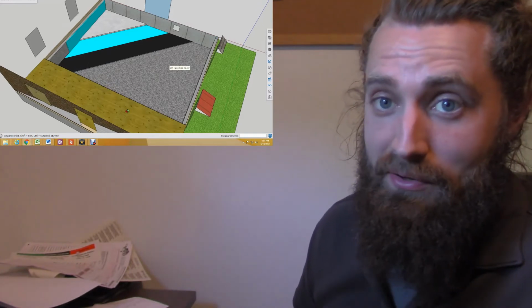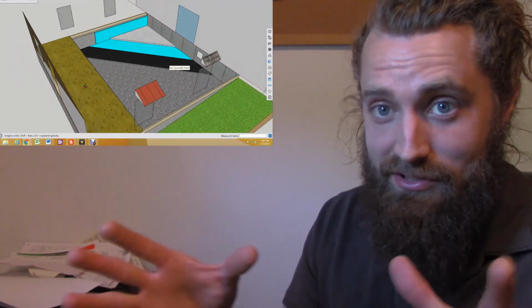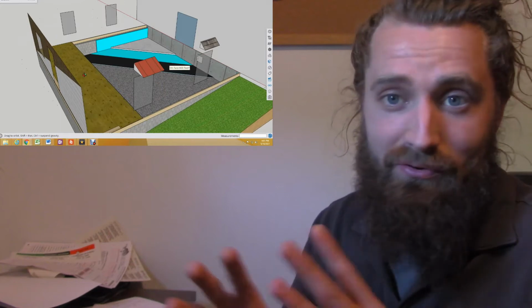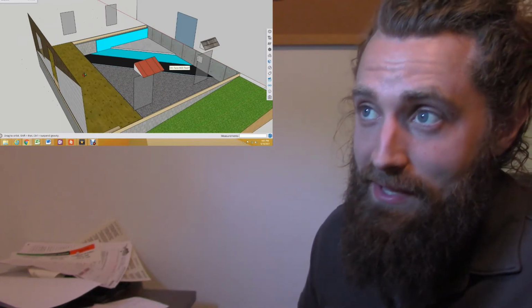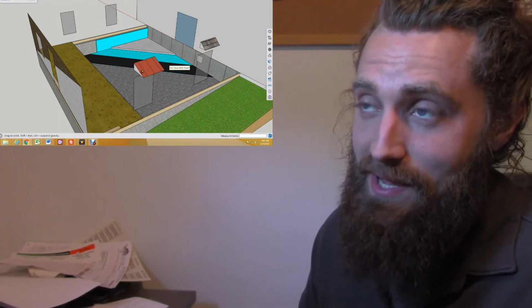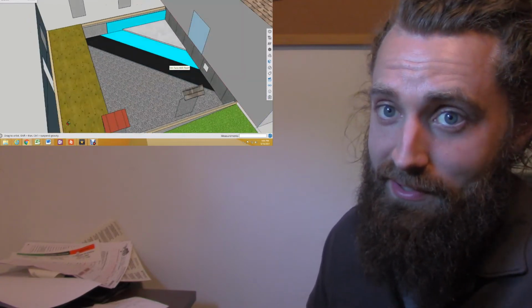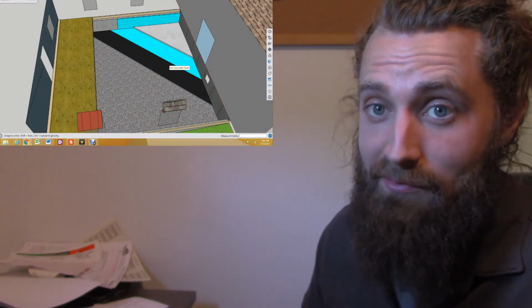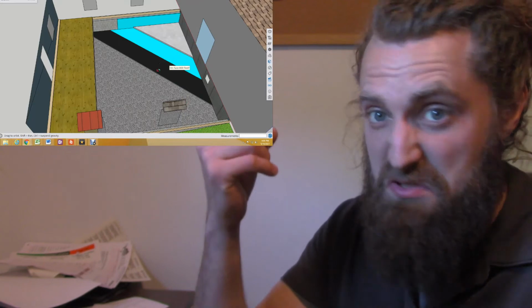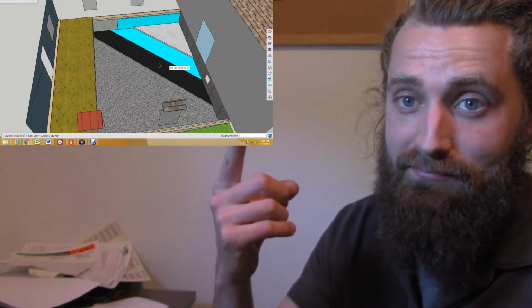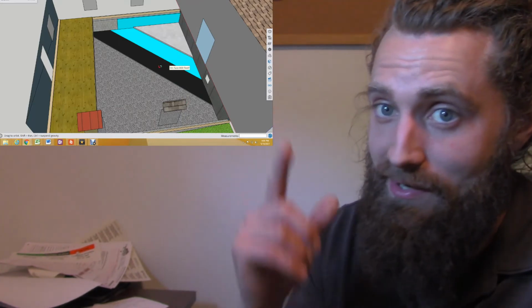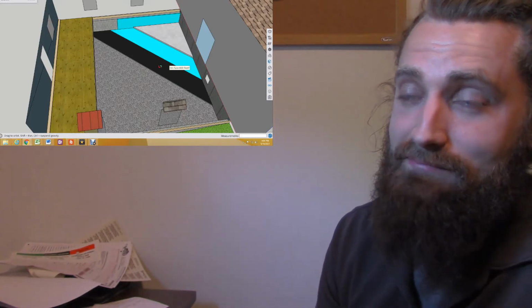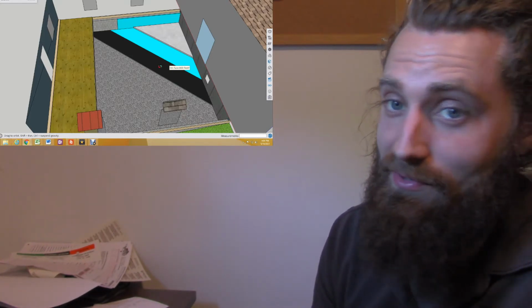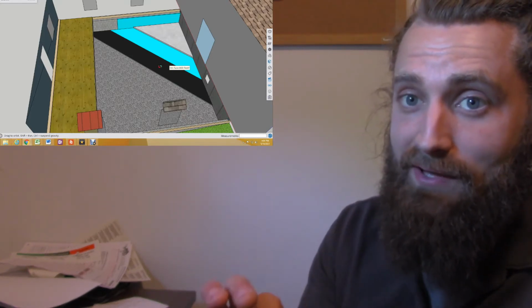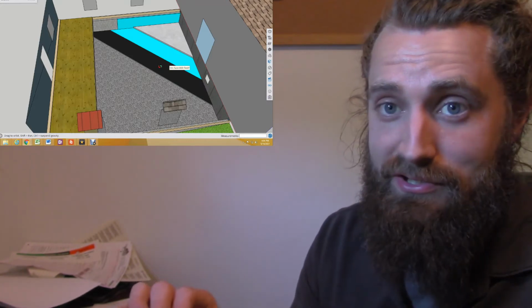Also, without knowing the overall construction, I have no clue at all. It is very possible that we could take an addition like this, a 30 by 30 addition, and supply it with one 7 or 8 inch supply and one 7 or 8 inch return, and it will maintain. That is very, very possible, and I'm not even kidding. It all depends on the construction of it.